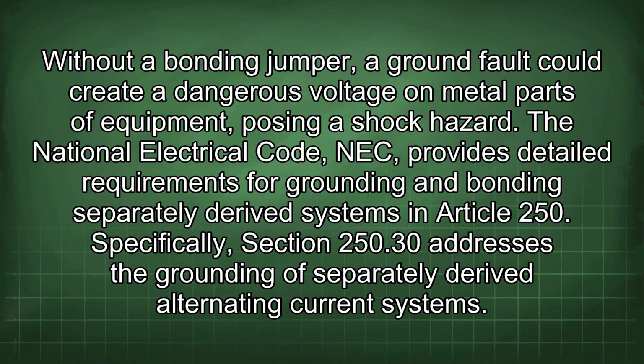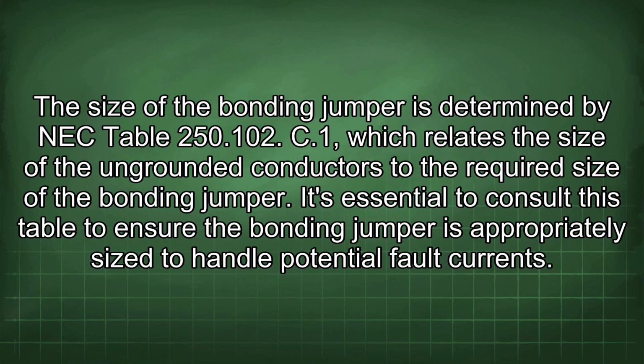Specifically, Section 250.30 addresses the grounding of separately derived alternating current systems. The size of the bonding jumper is determined by NEC Table 250.102(C)(1), which relates the size of the ungrounded conductors to the required size of the bonding jumper. It's essential to consult this table to ensure the bonding jumper is appropriately sized to handle potential fault currents.